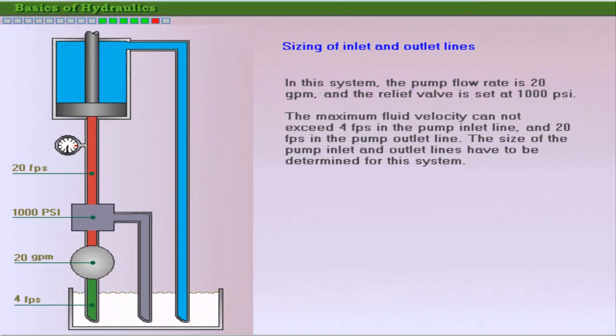We will use an example to discuss the sizing of input and output lines in a hydraulic system. The system shown in the figure has a flow rate of 20 gallons per minute, and the maximum pressure in the system is limited to 1000 PSI. Size the input and output lines if the velocity of oil in the inlet line cannot exceed 4 feet per second, and the maximum velocity in the outlet line cannot exceed 20 feet per second.